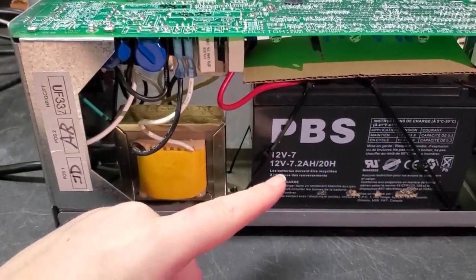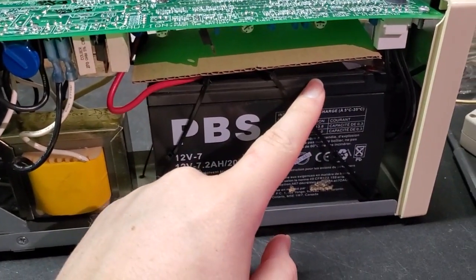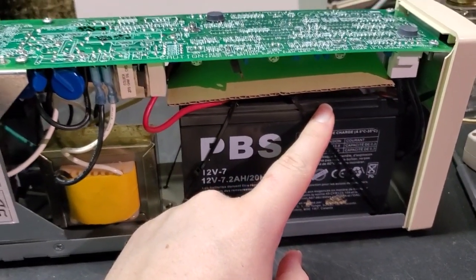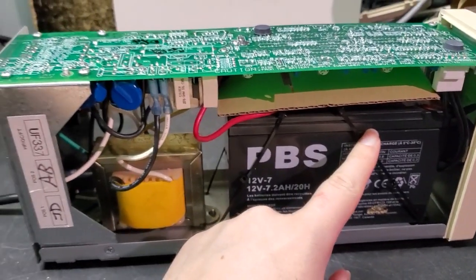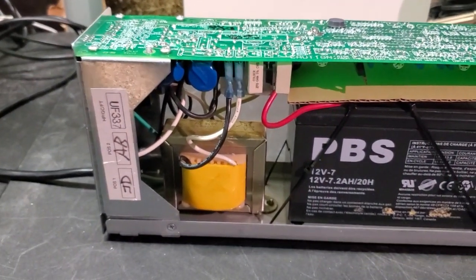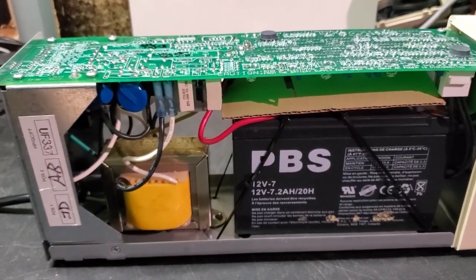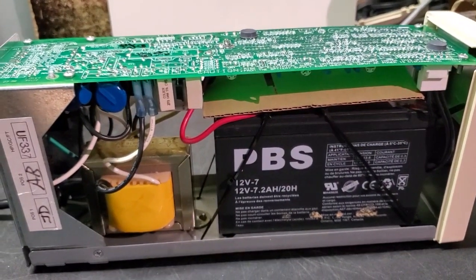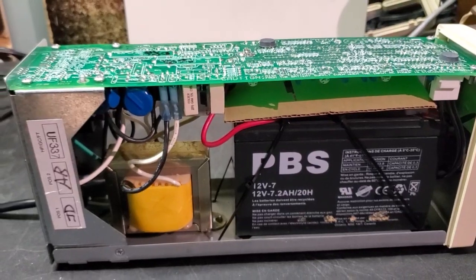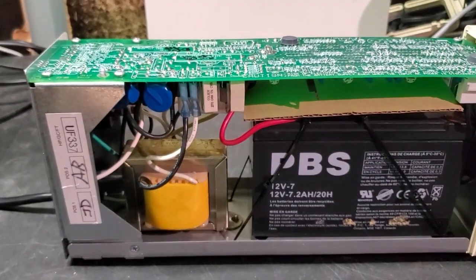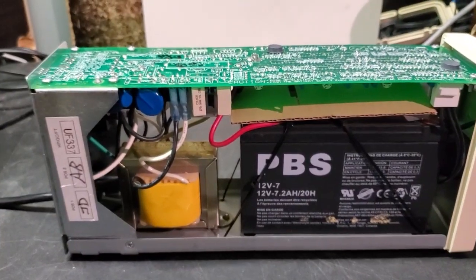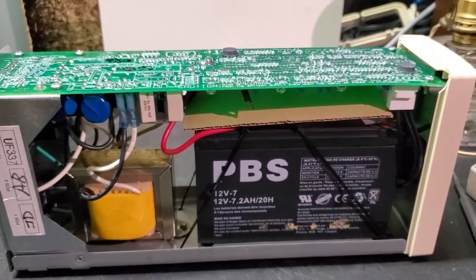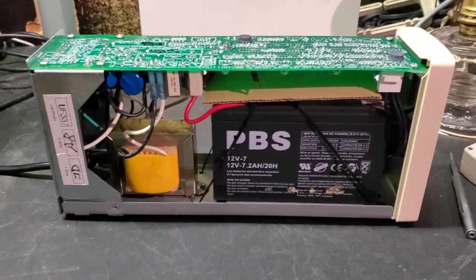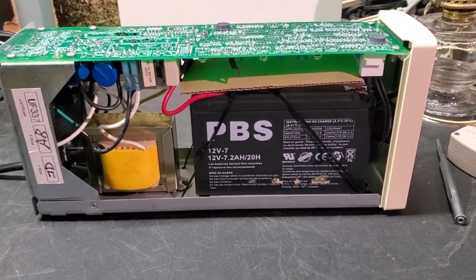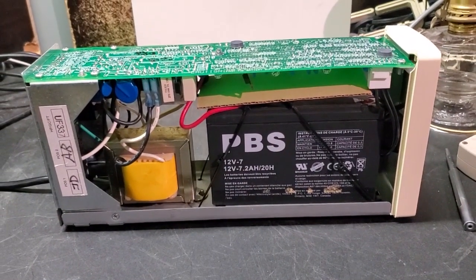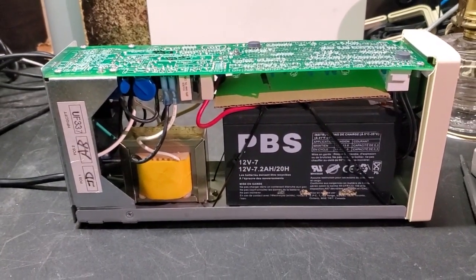When I first got this thing, I actually put a multimeter in series with the battery to measure the current drawn from the battery, and I found the inverter to be about 60% efficient, which is actually right on par for stuff like this. With no load on it, running on the inverter draws about 800 milliamps of current. And I suspect that with a full load, the inverter would be drawing close to 15 amps of current, which is not bad at all, and of course is the reason why they could make this thing a 12 volt unit rather than a 24 volt unit like the larger UPSs.